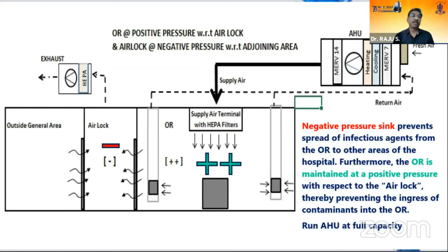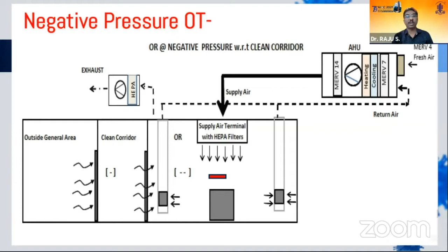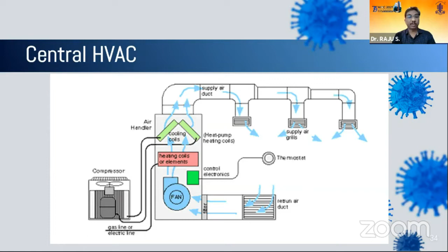As far as the negative pressure OT is concerned, this would be required only if you're treating COVID positive patients. And most of us may not be doing this, so this will be restricted to institutes. Here, the same OT will have to have another powerful exhaust so that it removes the air faster than what is supplied, with respect to the surrounding area. Hence it becomes a negative pressure, and the air would be coming from the clean corridor into the OT. As far as the central HVAC systems are concerned, these are actually very complicated. I will not delve into them. It is better to consult an air handling expert if you have to change anything in these systems.